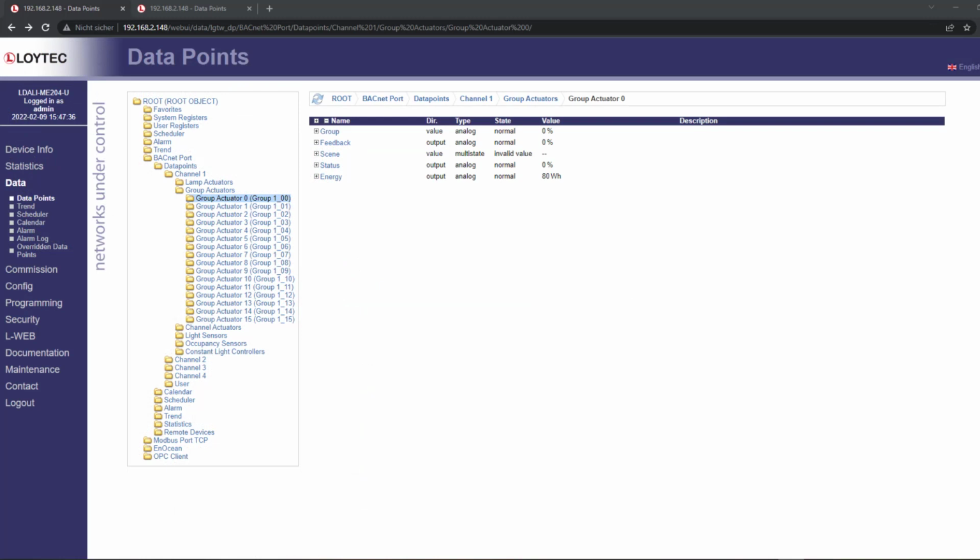Application side, the value can only have been written from our DPAL layer. How I came to this conclusion will be seen later on. The value therefore must have been written via the network, for example BACnet or OPC, or on the data point itself, for instance via the WebUI, a local connection, or a math object.